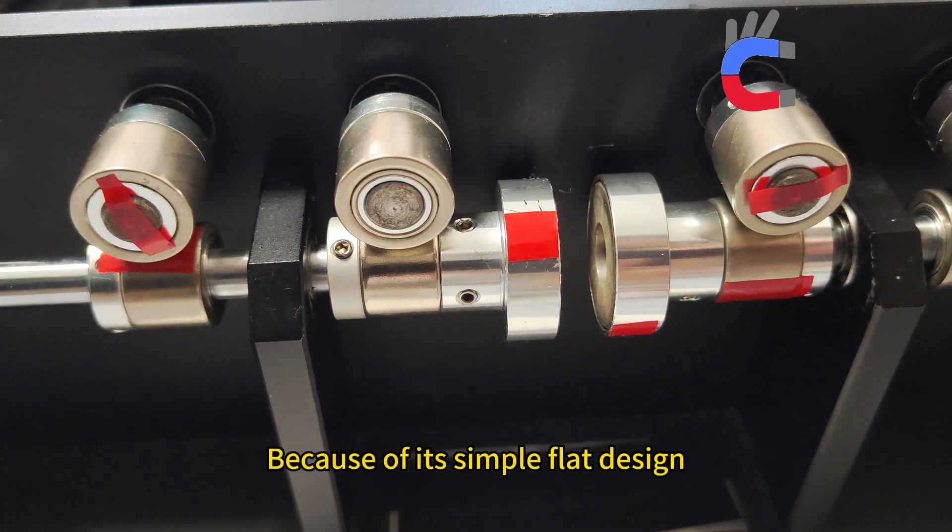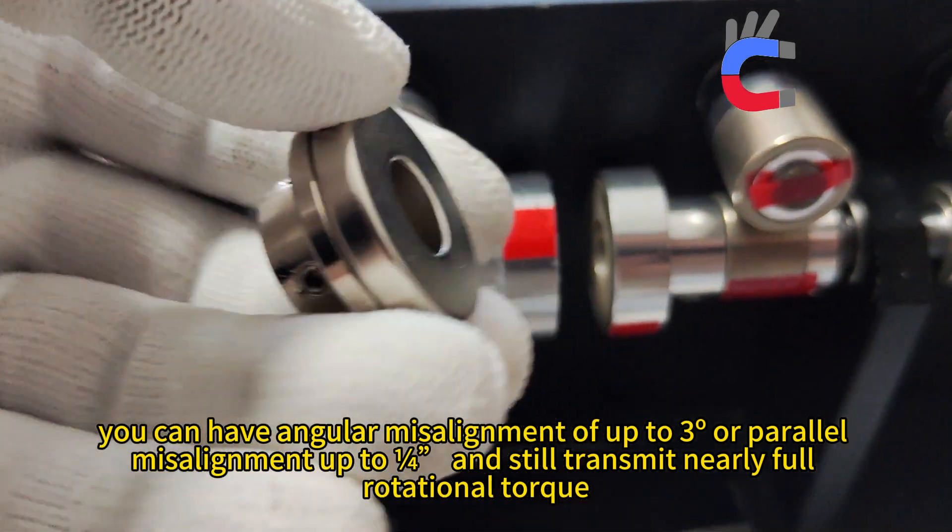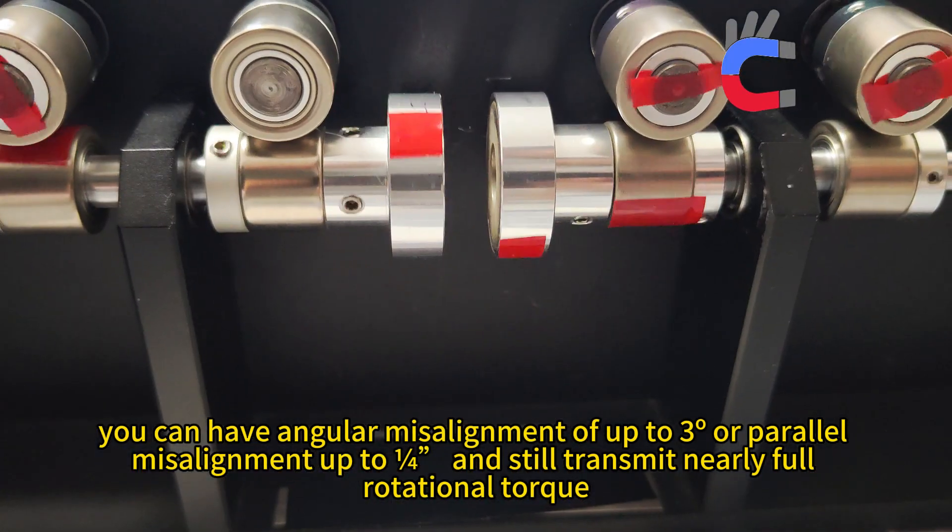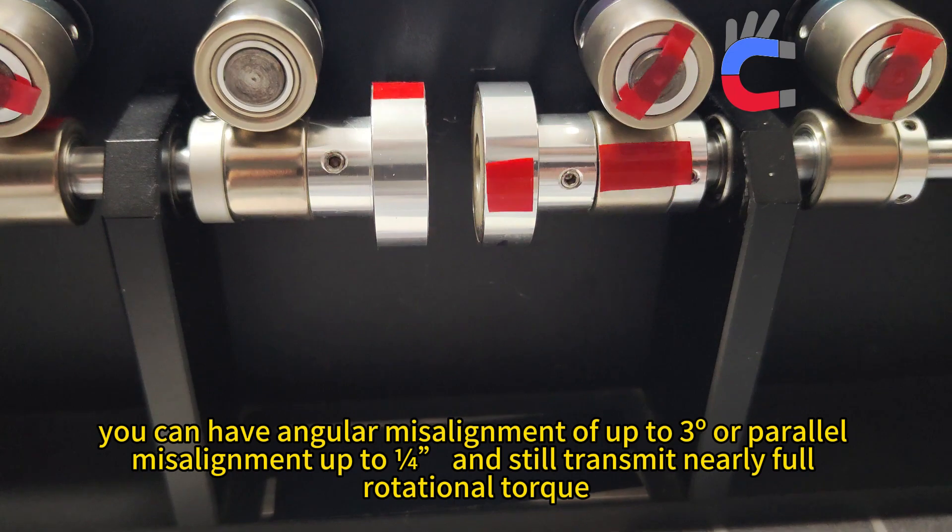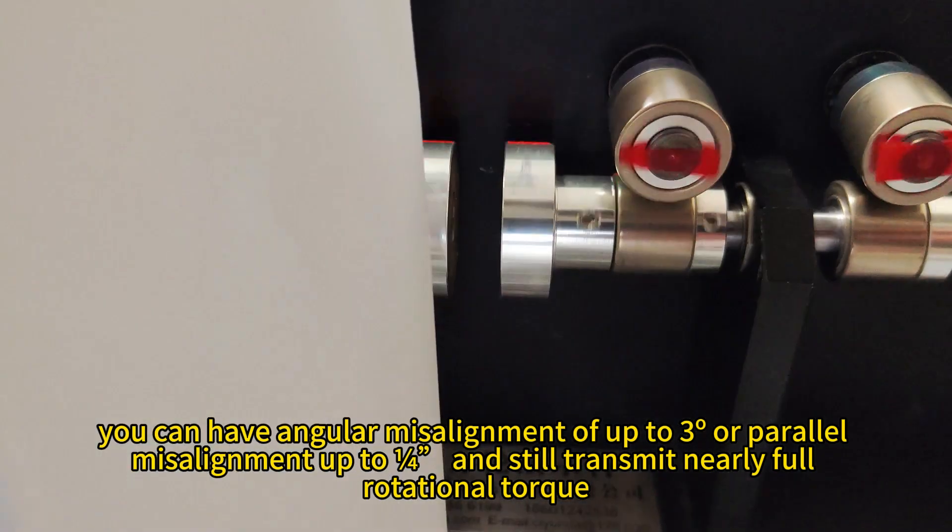Because of its simple flat design, you can have angular misalignment of up to 3 degrees or parallel misalignment up to one-fourth inch and still transmit nearly full rotational torque.